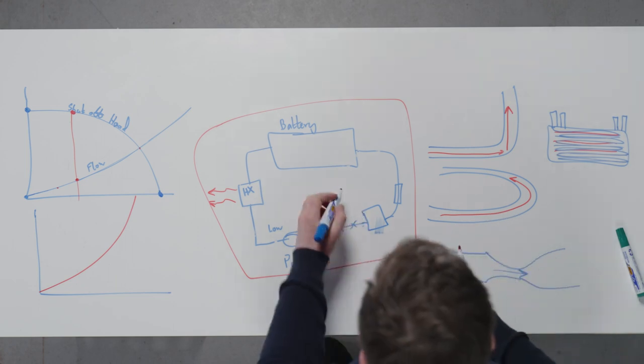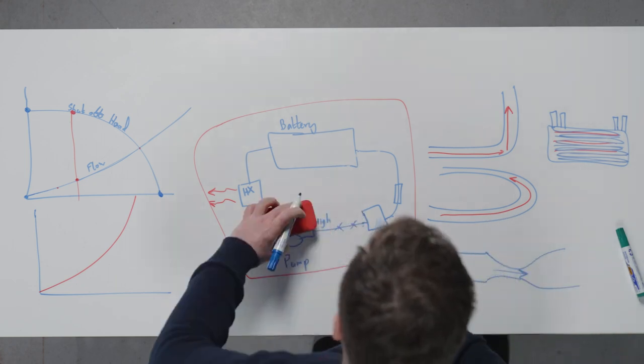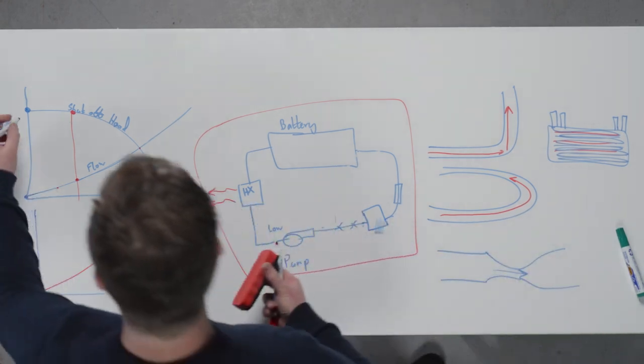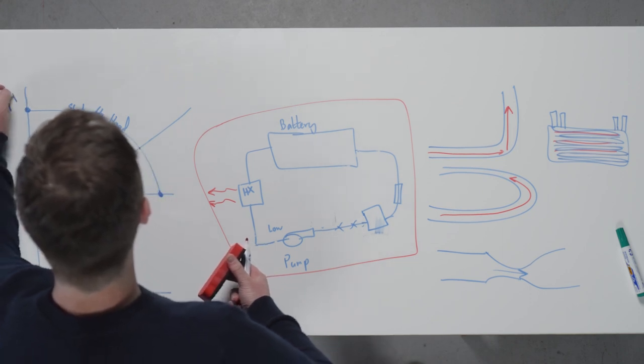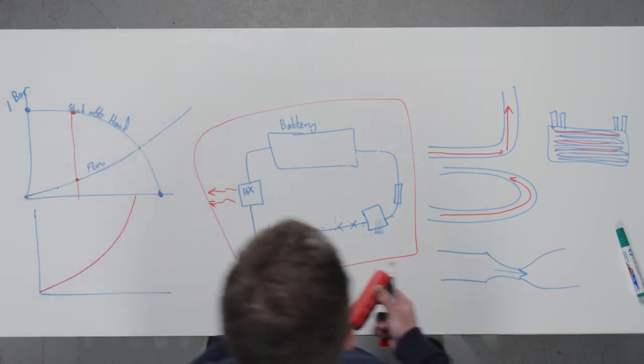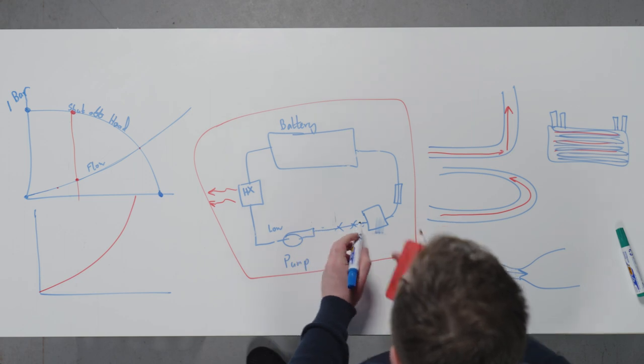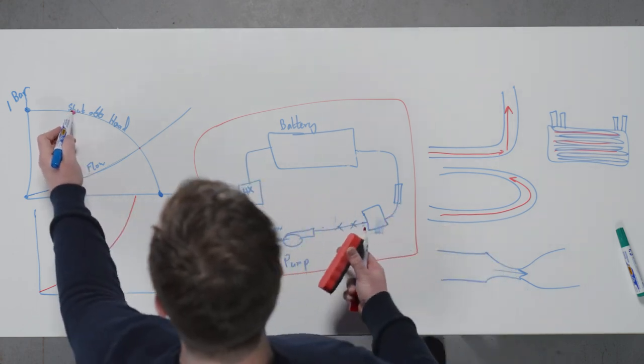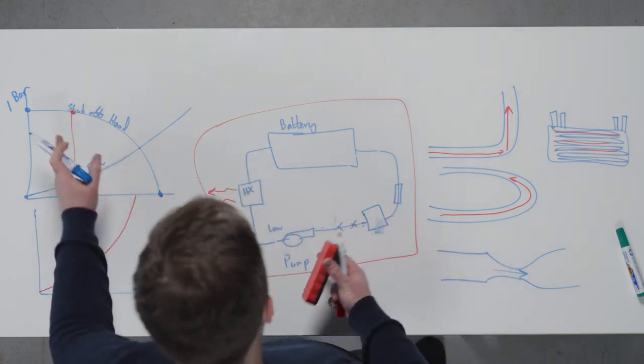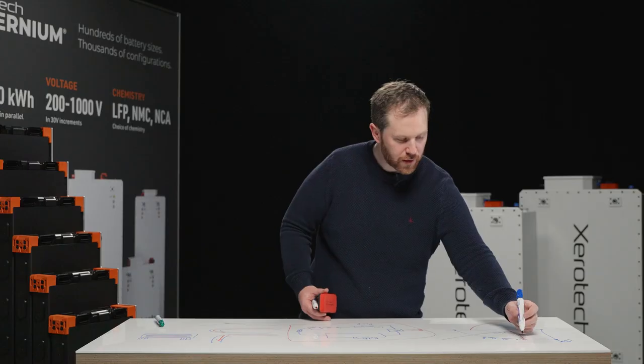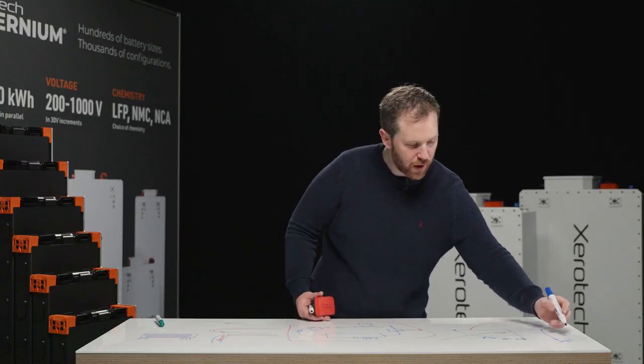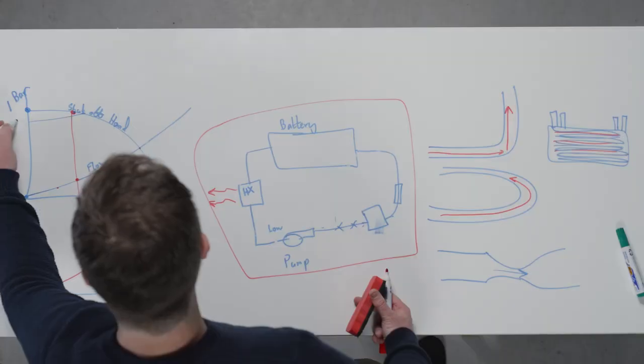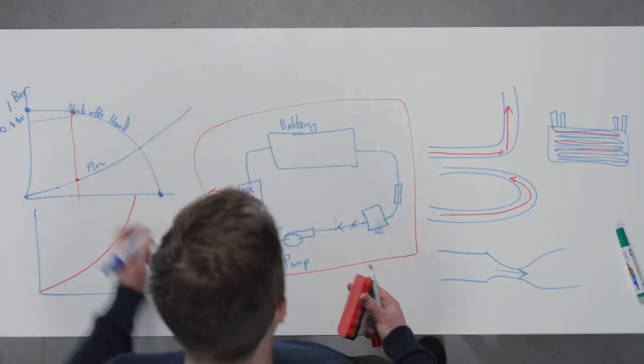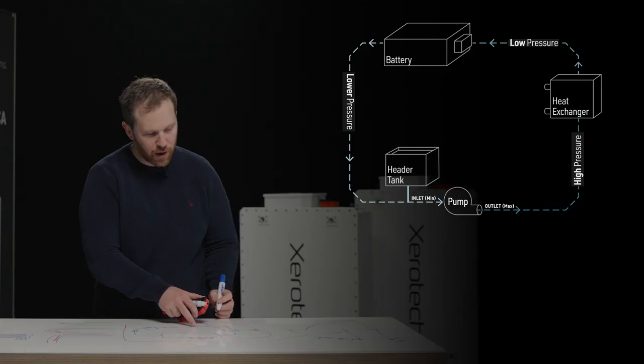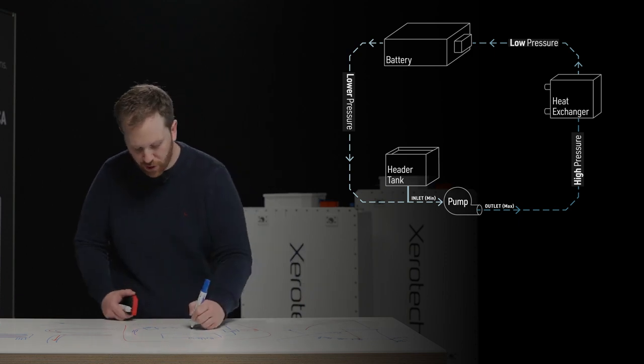the pressure here, let's use some real numbers. Let's say our pump has a shut-off head of 1 bar. It means that the pump in this case here will be developing a higher pressure somewhere along this curve. It'll have some flow rate going through it. So let's say it was at this point here and we go across, it might be 0.8 bar. That's the peak pressure the system is delivering. So on the outlet point of this pump, it has 0.8 bar.